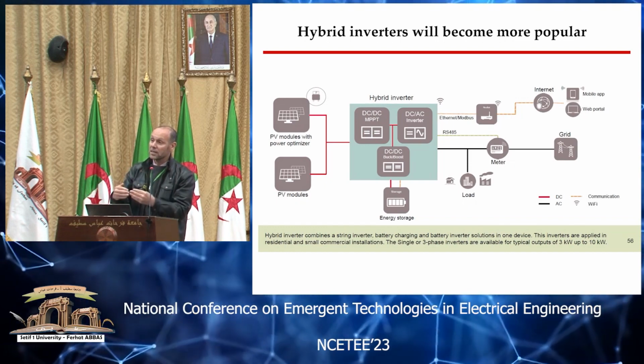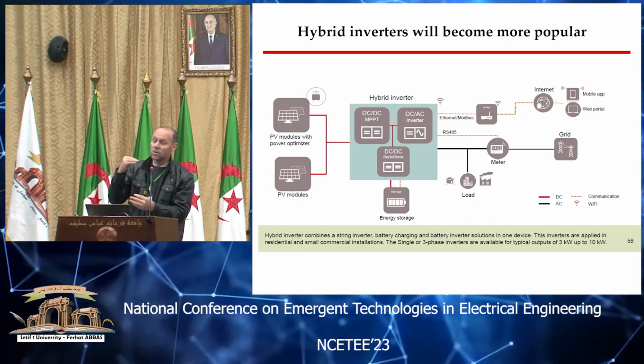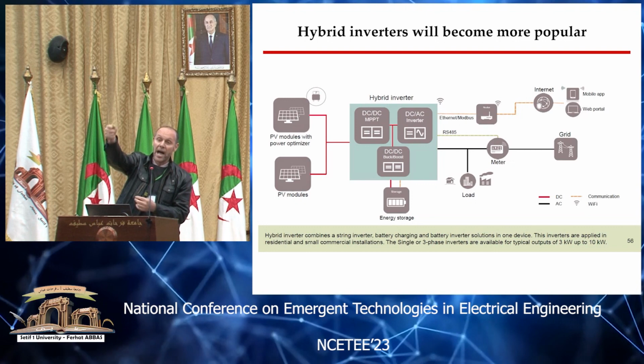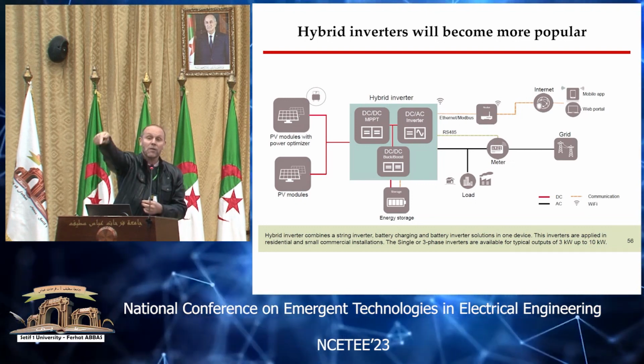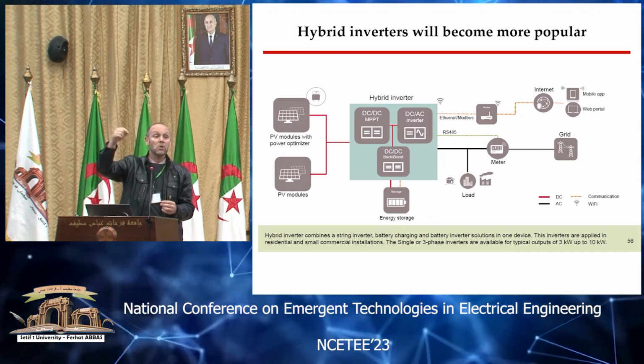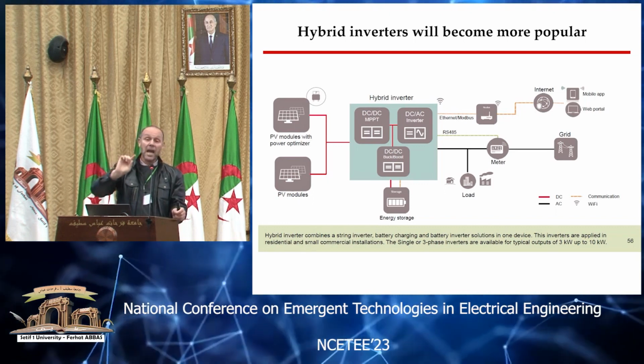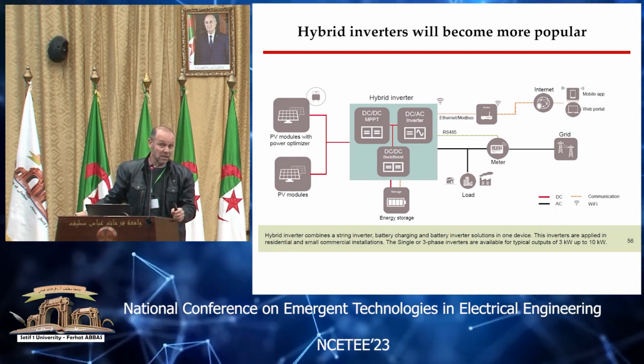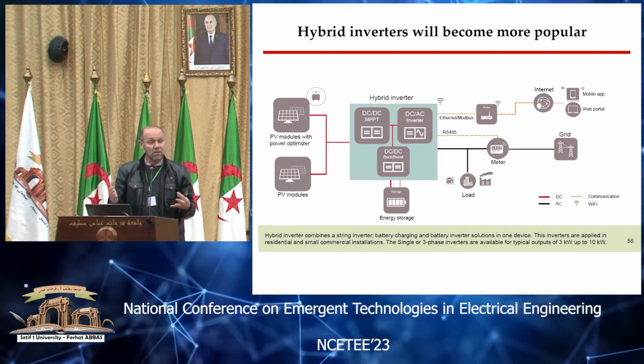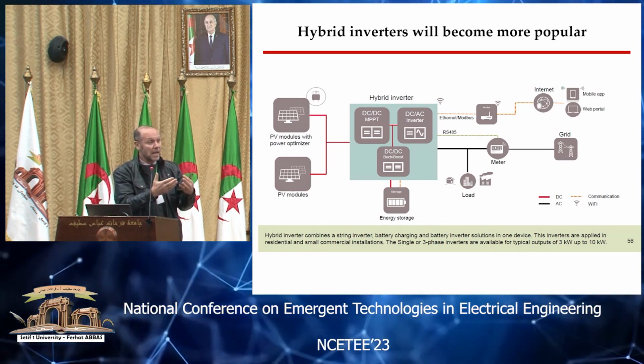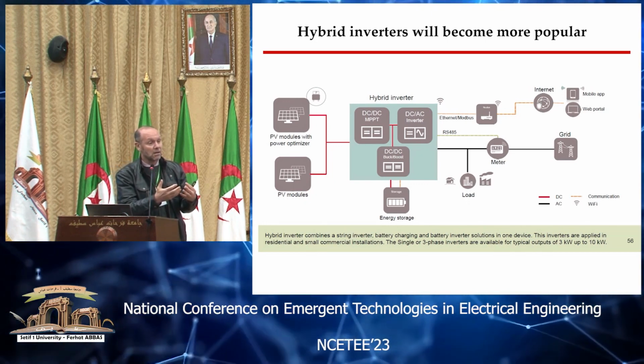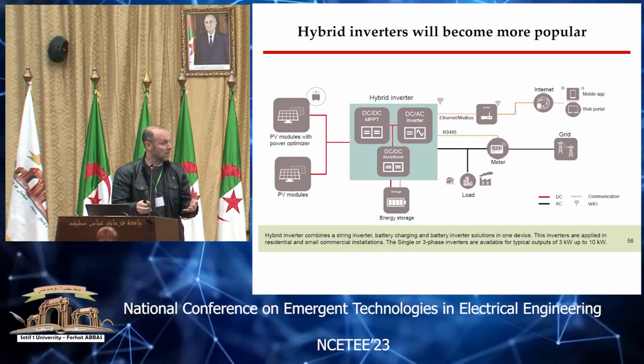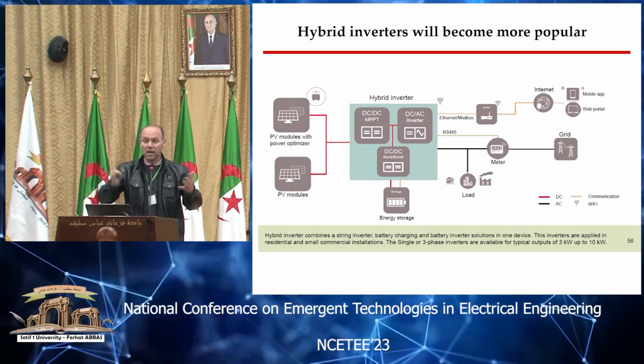But the new inverters, and this is also a very hot topic, are grid-forming inverters, meaning the inverter should help stabilize the frequency and voltage of the grid. You connect to any voltage, any frequency, and it helps stabilize the grid, because the grid is becoming less what you'd call inertia-heavy, meaning there's no gas power plant, since everything is inverters or renewables.